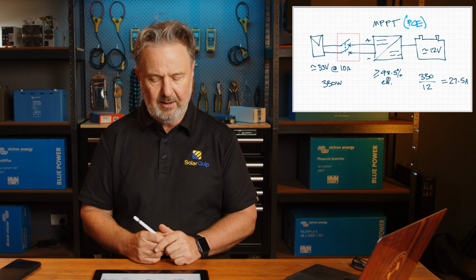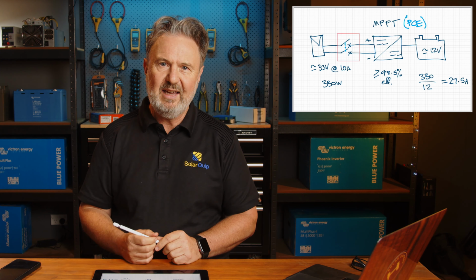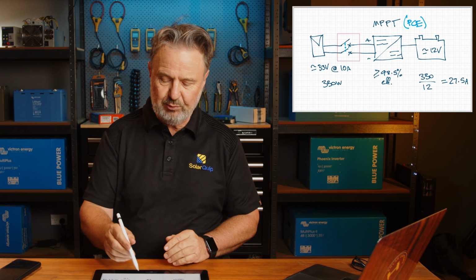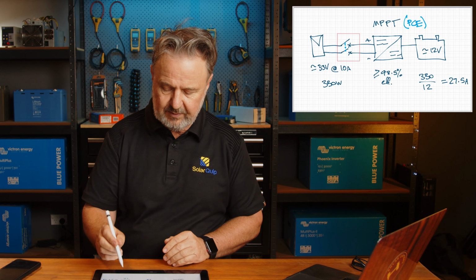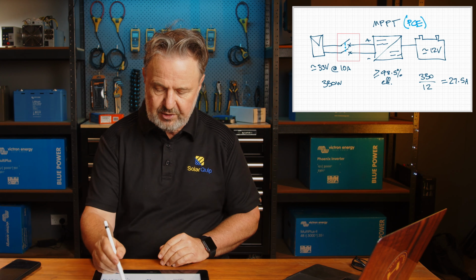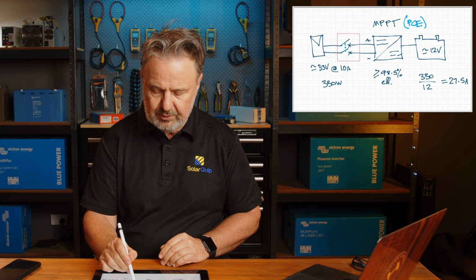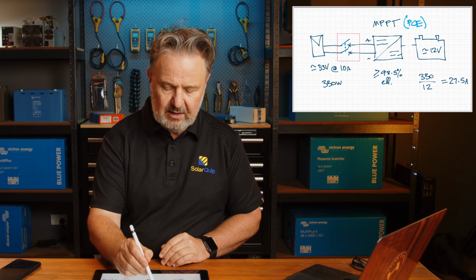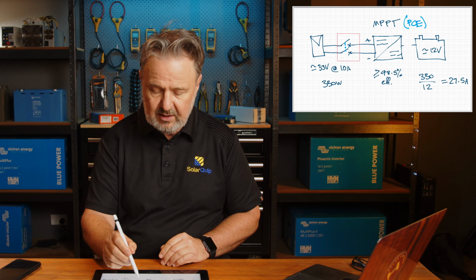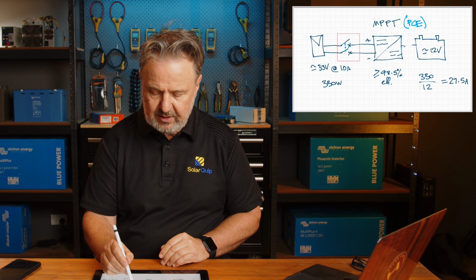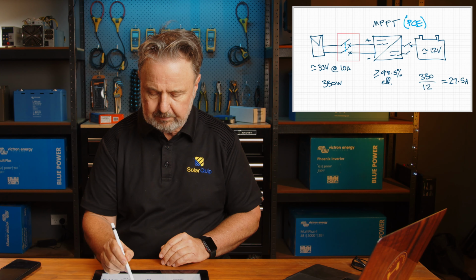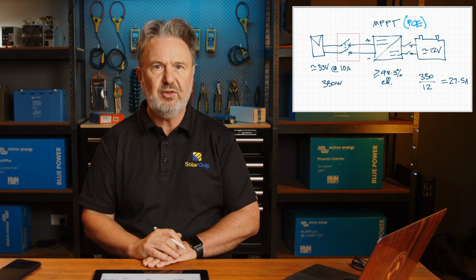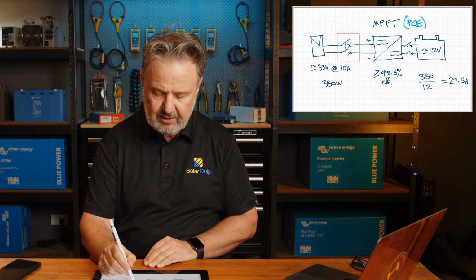Now you can actually have isolation without overcurrent protection, but I've shown a circuit breaker, hence the little X, showing overload protection, and that means it can protect against reverse current flow from the battery system. So if our battery was to have a fault, it would cause current to flow. That means we also need a means of isolation and overcurrent protection at the battery end. So I'm going to show that as well. There we go. We've actually got two points of isolation and overcurrent protection.